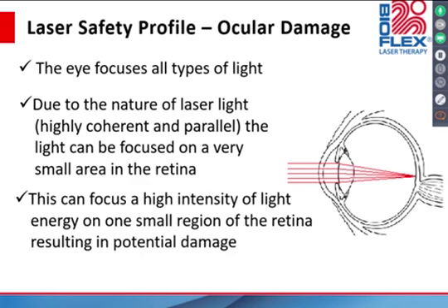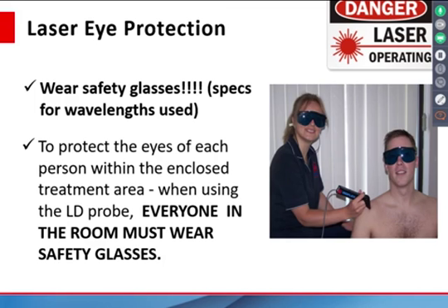So that's the main concern with respect to using laser diodes that are above the 5 milliwatt to 500 milliwatts. Most lasers under 5 milliwatts aren't considered overly harmful to the eye. So if you think of a laser pointer, that kind of thing, you don't need to wear protective eyewear with those lasers. However, as you get into the threshold of 3B especially, that's where you need to have special eyewear. So the safety glasses are specified according to the wavelengths used for the specifications of that medical device.